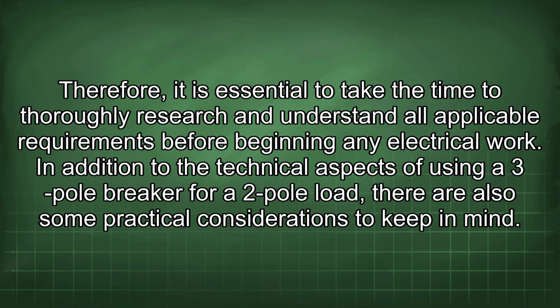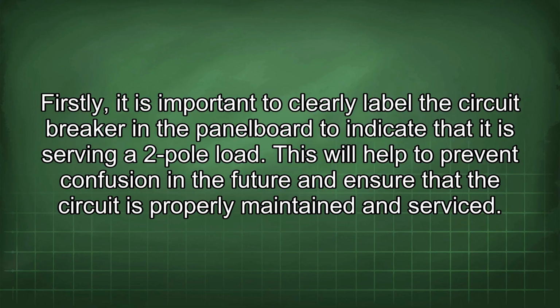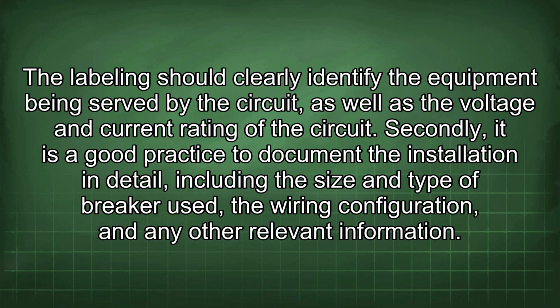In addition to the technical aspects of using a 3-pole breaker for a 2-pole load, there are also some practical considerations to keep in mind. Firstly, it is important to clearly label the circuit breaker in the panel board to indicate that it is serving a 2-pole load. This will help to prevent confusion in the future and ensure that the circuit is properly maintained and serviced. The labeling should clearly identify the equipment being served by the circuit, as well as the voltage and current rating of the circuit.